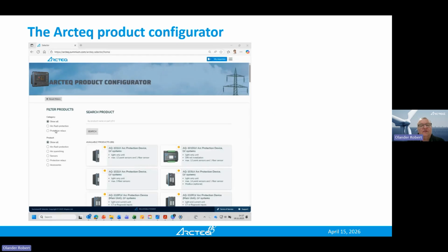Here is a short video showing just the general idea. So you can choose the application. You can filter the devices first, then you choose the feeder protection device, then you start choosing the functionality that you need, like digital inputs, as many as you need. Digital output, there is an info telling what it does, then you can choose it, and so on. And then you can choose milliampere input, then you can choose communication, like we do here, like an LC redundant fiber.